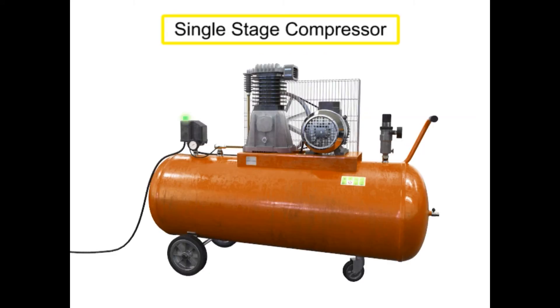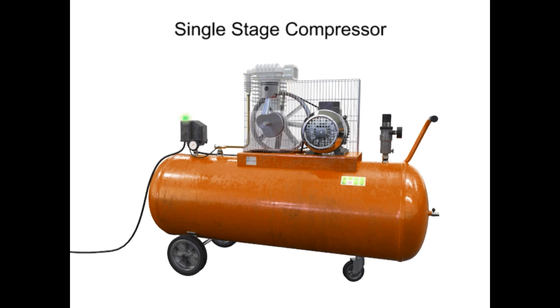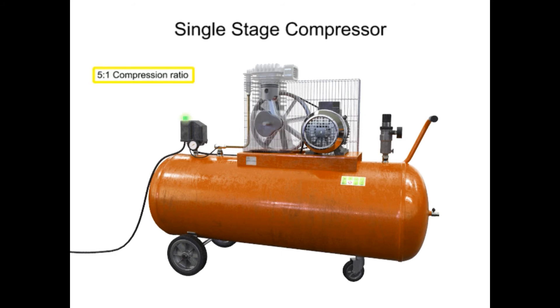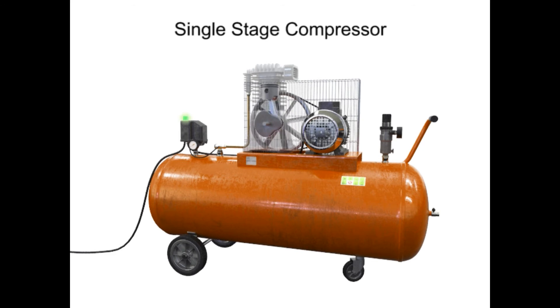This is a single-stage compressor. It has only one piston and cylinder and compresses the air in only one stage. A single-stage compressor typically has a compression ratio of 5 to 1 with an output pressure of about 50 to 75 PSI. As air is compressed, it becomes increasingly hot.